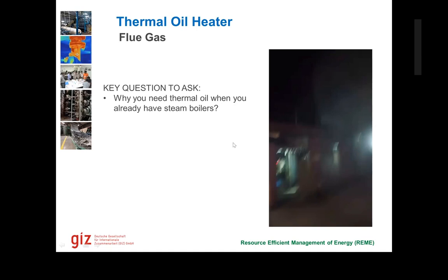So we thought that maybe the spray nozzles of the burner are not working properly and they're spraying too much furnace oil for burning. And maybe this is going out as particles, and when it comes out, it starts burning. So we had to actually open everything, and we figured out that there was a lot of soot accumulated in the exhaust. It was so much accumulated, then it started coming off and going out. And since the temperature was very high, when it came out, it started flashing in the air.